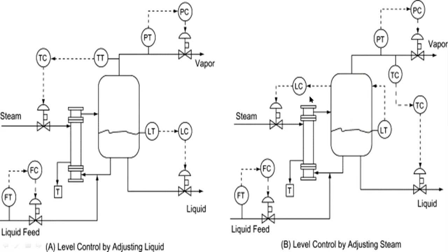So this is another example where we have the steam that is coming in through the heat exchanger going to the evaporator, and feed is coming here at a controlled level and a controlled flow, and steam is coming here. Then the vapor is going out to another heat exchanger, where your next stage has a level transmitter and controller. Whereas here in the evaporator you are controlling the temperature, and this temperature controller is given to the steam controller. The level transmitter and level control is given to the flow controller, which is taking out the liquid product from the bottom of the evaporator.